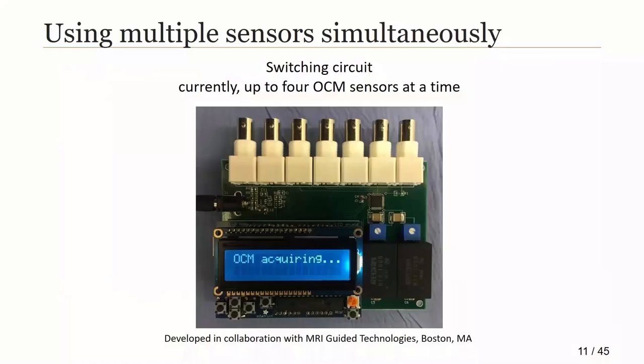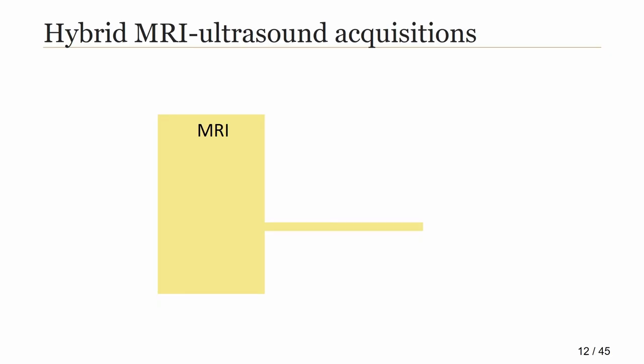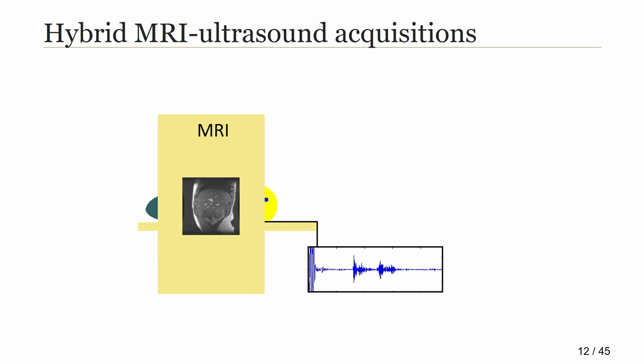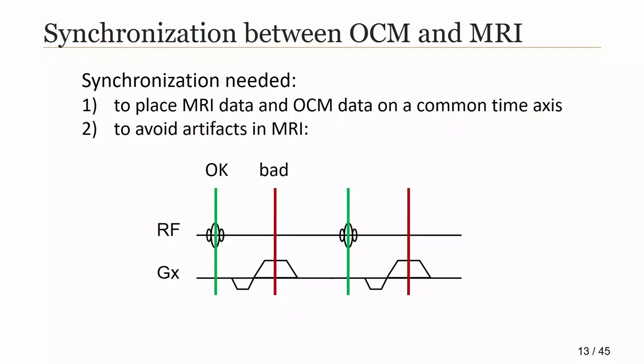We also developed a small circuit that allows up to four of these sensors to be used simultaneously. The general idea is that one or more sensors are applied to a subject or patient and accompany them inside the MR scanner. At that point, we have two streams of simultaneous data coming in — one from MRI and one from ultrasound — meaning we have a hybrid MRI-ultrasound acquisition. We call our sensor OCM, standing for Organ Configuration Motion.